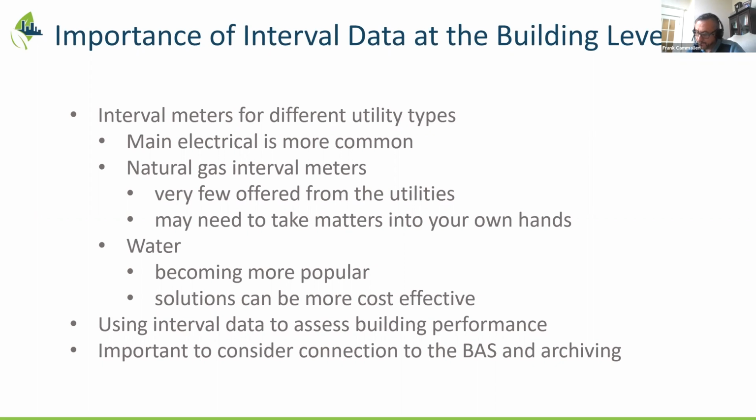Yeah, they've been extremely useful in troubleshooting and researching different ways to save energy, because it's pretty near real-time data. So when we were running the Battle of the Buildings competitions amongst our community centers, I used that regularly. It's much faster than waiting for bills to arrive 2 or 3 months later. We've also used it to identify loads that aren't shutting off overnight.